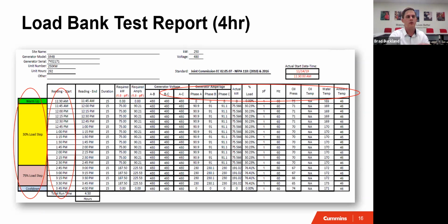So when you would get these, a lot of companies have their own version of formatting all this, but everyone should have this across the industry as far as a form to hand you, so you can see it as well. A lot of people keep records of them, just that way in case someone asks you about it, you have, hey, we've tested this for 3 years with no problems. And it just creates a history for the gen. So you're not working off of no information, and you're eliminating guesswork, which is a big advantage of planned maintenance, eliminating guesswork, eliminating repair times, if any, and moving forward with a good as new gen.